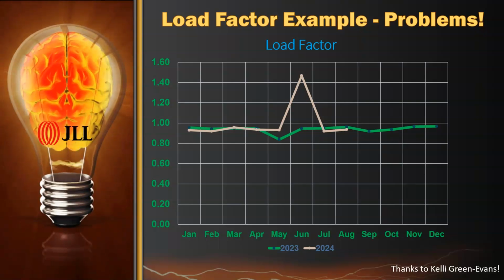Okay. So then you're going to reduce your load factor from this high level of 0.95 to maybe what you think it should be, 0.75. And then you'll back engineer: this is how many kilowatt hours will be saved. We're not going to change the demand at all. This many kilowatt hours will be saved. And that's how you can make this estimate of what you could save. That's right, yeah, interesting. Okay.